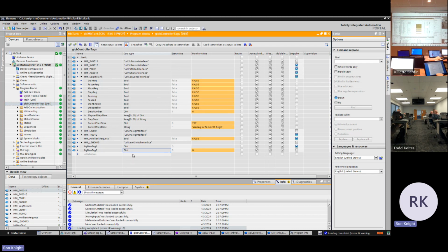Any questions on that workflow? By the way, if you're in doubt, if you've got a running PLC and you think, man, I don't know what this is going to do, launch it in PLC Sim. The behavior in PLC Sim is exactly what's going to happen inside the PLC. So test it. See what's going to happen before you do it to a live PLC. PLC Sim is free. It's always there. Just hit start simulation. You can see what happens. That's what I do. And if it breaks your laptop, probably don't value it. Exactly. Good rule of thumb. If your laptop blue screens, don't do it.